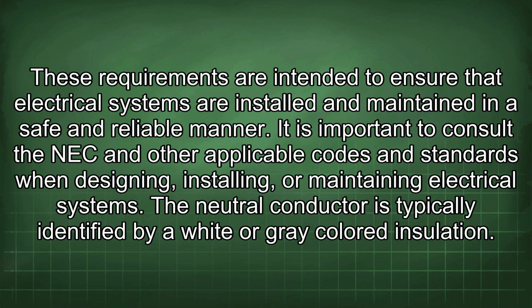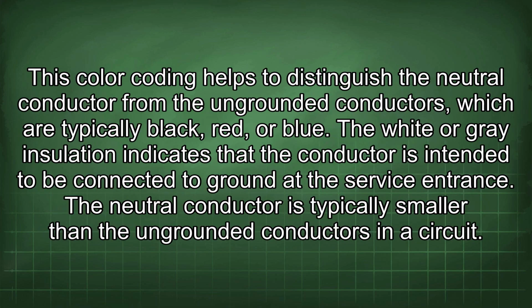The neutral conductor is typically identified by a white or grey colored insulation. This color coding helps to distinguish the neutral conductor from the ungrounded conductors, which are typically black, red, or blue. The white or gray insulation indicates that the conductor is intended to be connected to ground at the service entrance.